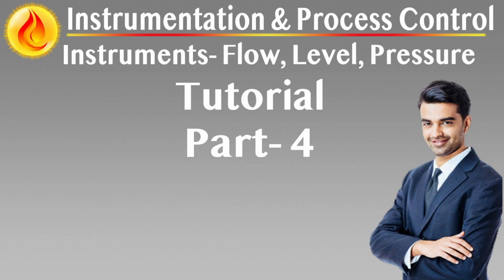They are particularly effective where pressure and temperature vary, but gas composition remains relatively constant, eliminating the need for additional compensation instrumentation. Their no moving parts design, low pressure drop, and insertion style availability make them ideal for ventilation air, nitrogen purging, combustion air, and flue gas measurement. Purge gas and tracer flow verification, analyzer shelters, flare monitoring, and leak detection and submetering of utilities.